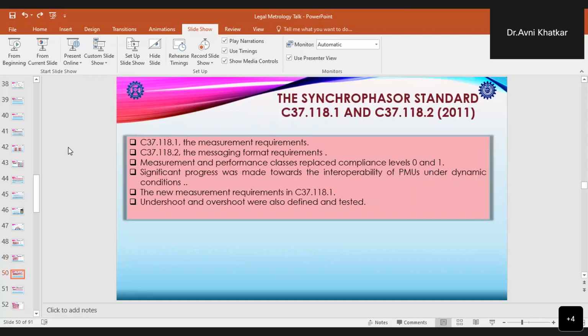So in 2011, this 2005 standard came apart to form two different standards, that is IEEE C37.118.1 and C37.118.2. The C37.118.1 standard formed the measurement standard, whereas the .2 standard became the communication standard. In the measurement standard, the measurement and performance classes were included, and these performance classes replaced the earlier compliance levels, that is level 0 and level 1.